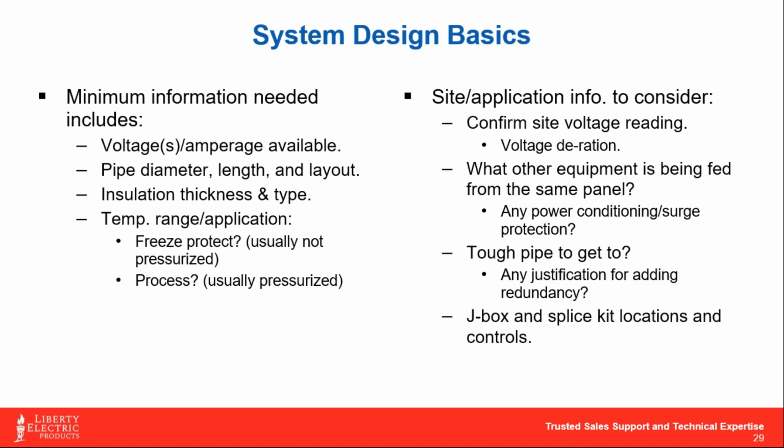Most manufacturers usually shoot for about a 20% safety or fudge factor they might build into it. Personally, I'll just say on behalf of ourselves, we shoot for more like a 10. Regardless, we don't want you to have a whole bunch of cable overage. And if we do our diligence on the front side of these designs, generally the materials really work themselves out to be quite accurate.